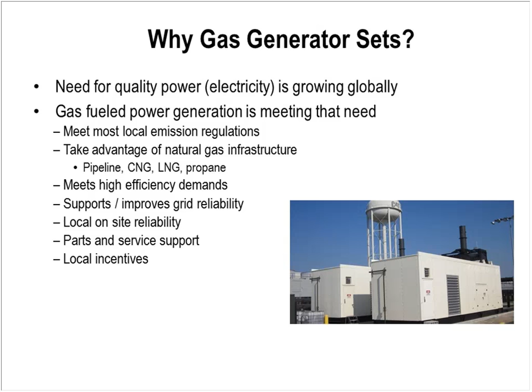From a power generation perspective, lower owning and operating costs are certainly there. Looking at maintenance, an oil change on a diesel engine is typically in the 250 to 300 hour range, depending on oxidation, nitration, and power levels for that engine. For a gas engine, it's not uncommon to be in the 2,000 hour range for an oil change.